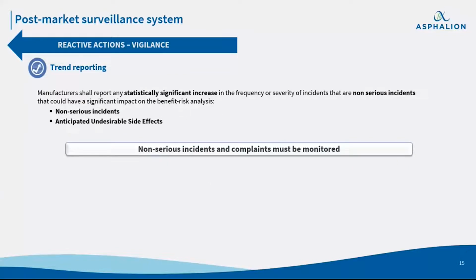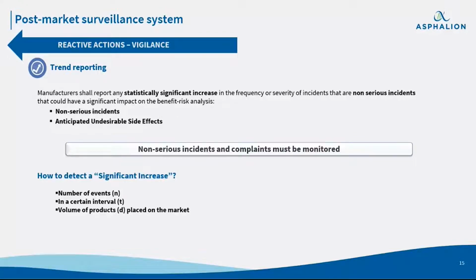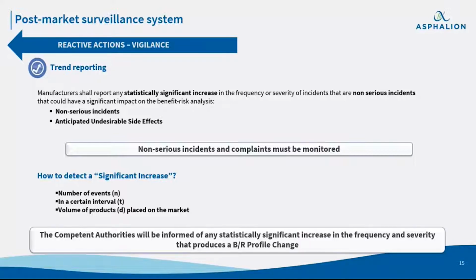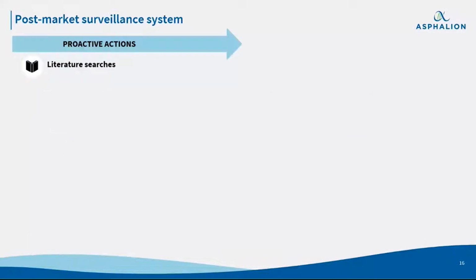As the last reactive actions, we have the trend analysis and reporting. Manufacturers should report any statistically significant increase in the frequency or severity of incidents that are non-serious incidents and that could have a significant impact on benefit risk analysis. So, non-serious incidents and complaints must also be monitored. But how can we detect a significant increase? By evaluating the number of events in a certain interval and taking into account the volume of product placed on the market. The competent authorities will be informed of any statistically significant increase in the frequency and severity that produces a benefit risk profile change.